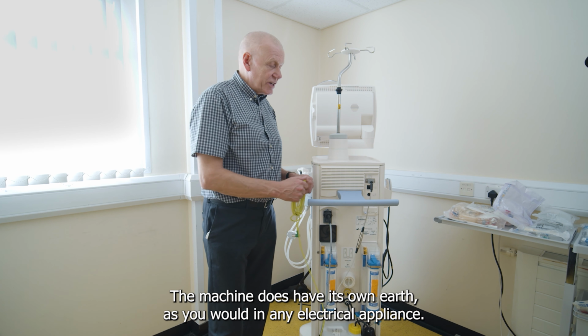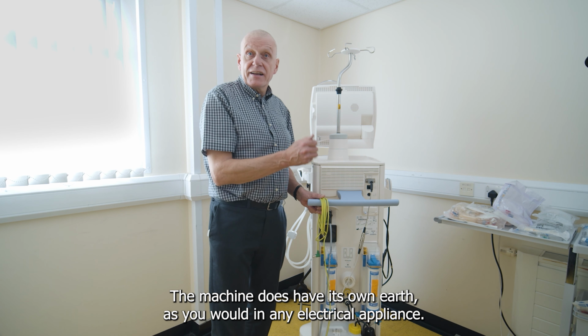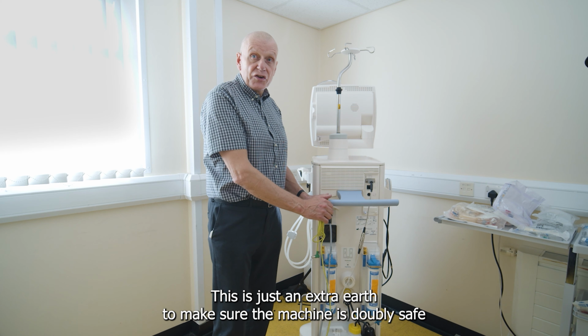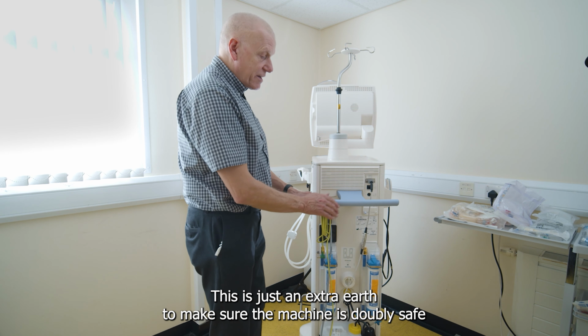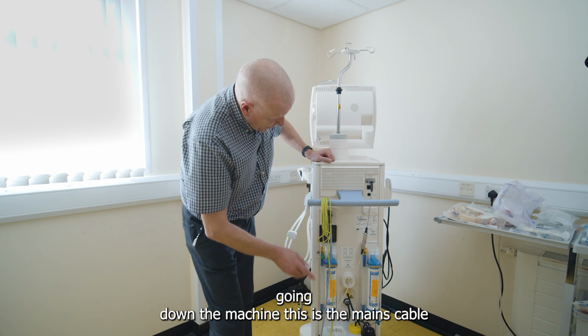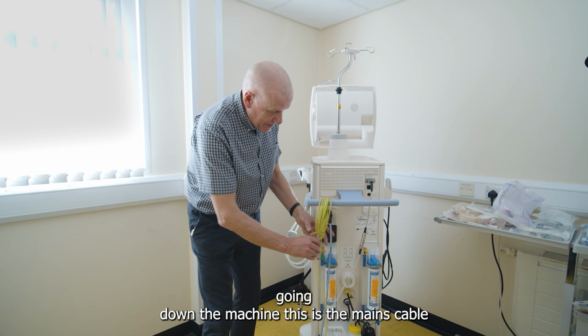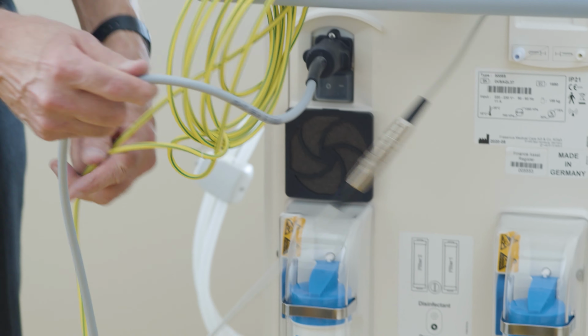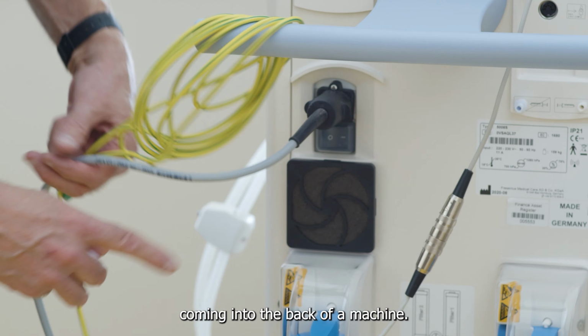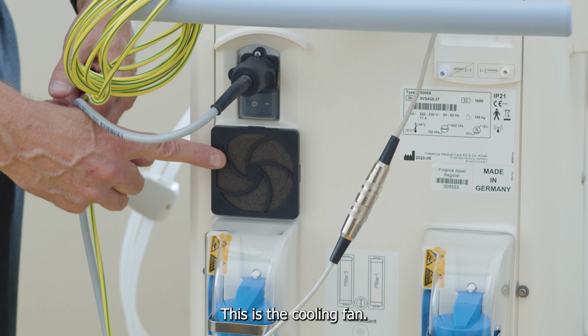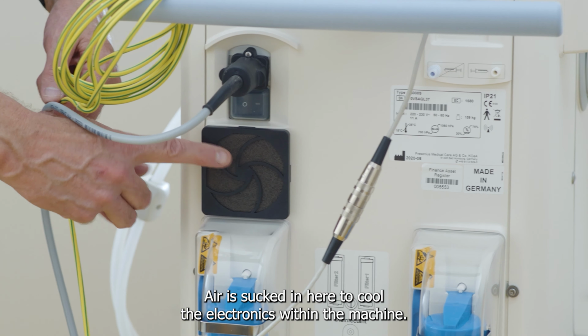Here we have what's known as the equipotential bonding cable. It's an extra earth on the dialysis machine. The machine does have its own earth, as you would in any electrical appliance. This is just an extra earth to make sure the machine is doubly safe. Going down the machine, this is the mains cable coming into the back of the machine. This is the cooling fan. Air is sucked in here to cool the electronics within the machine.